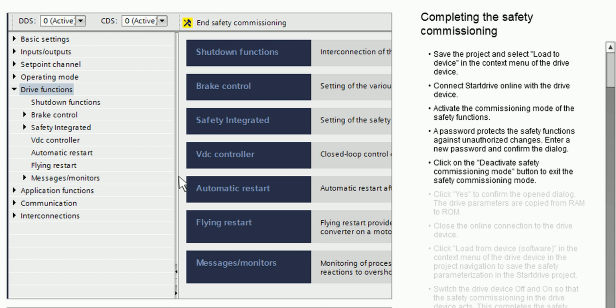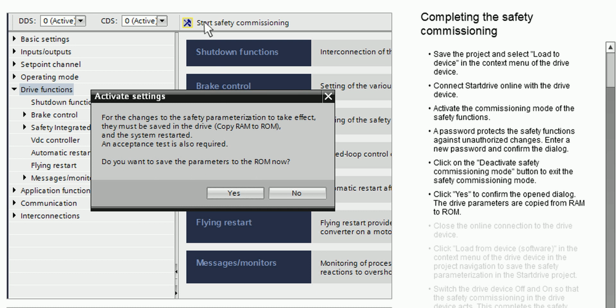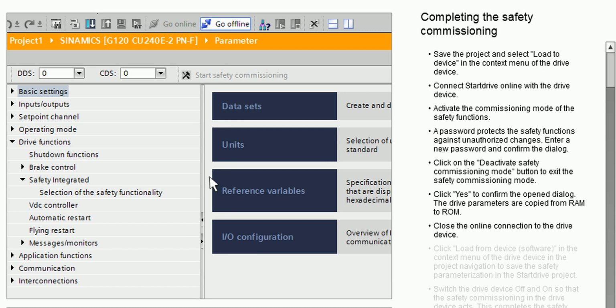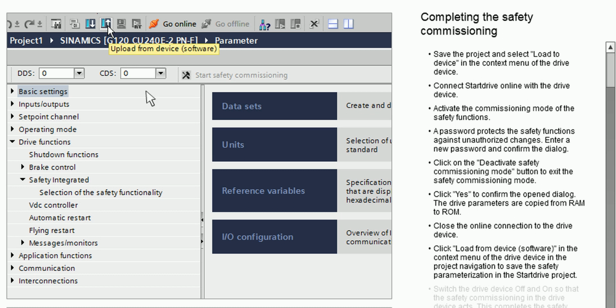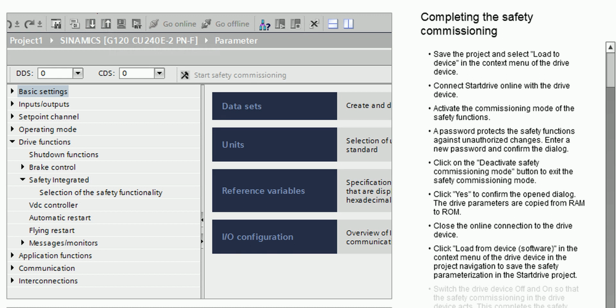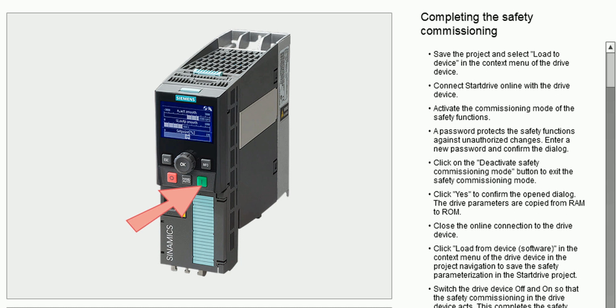Click on the Deactivate Safety Commissioning Mode button to exit the safety commissioning mode. Click Yes to confirm the open dialog. The drive parameters are copied from RAM to ROM. Close the online connection to the drive device. Click Load from Device, Software in the context menu of the drive device in the project navigation to save the safety parameterization in the Startdrive project. Switch the drive device off and on so that the safety commissioning in the drive device acts. This completes the safety commissioning.